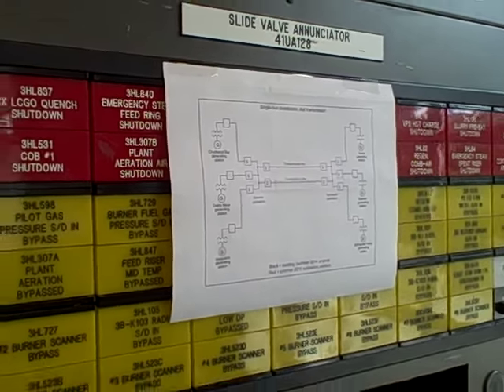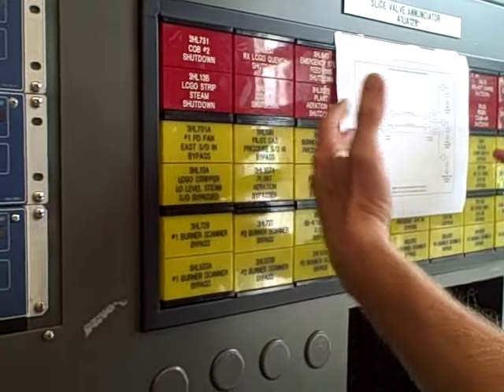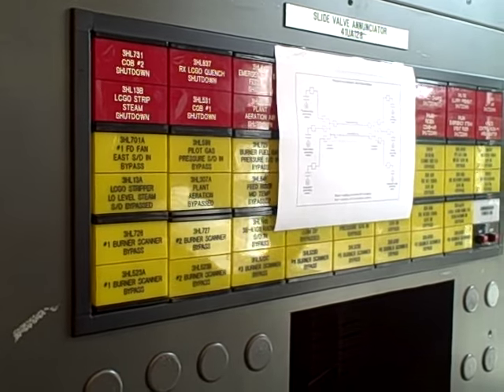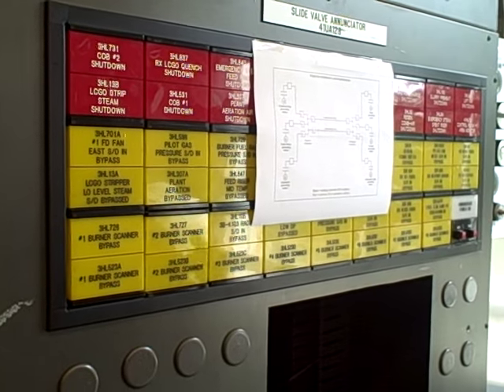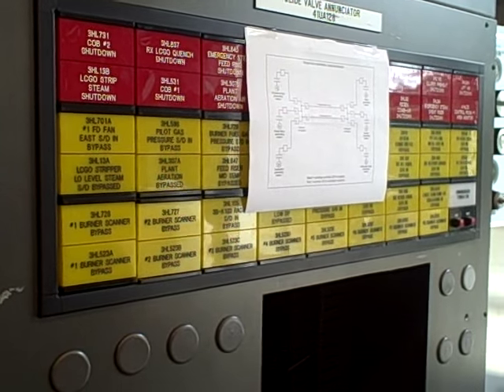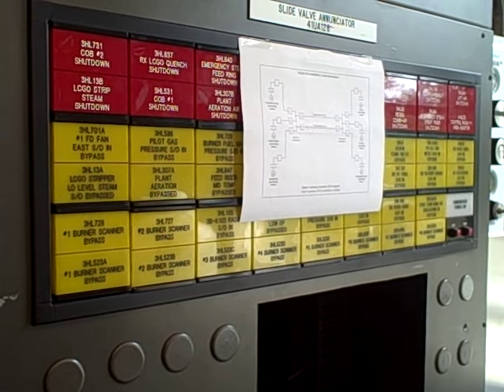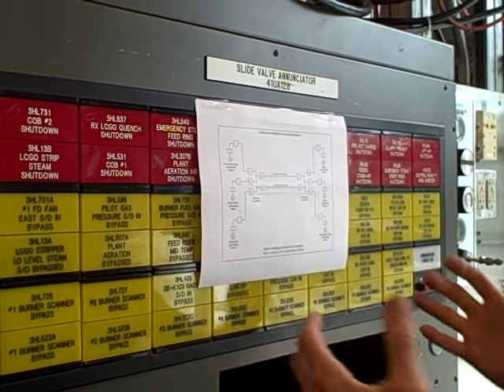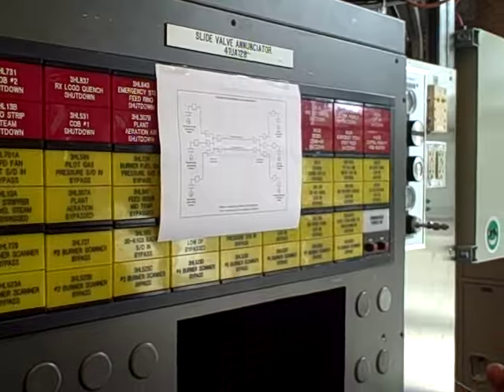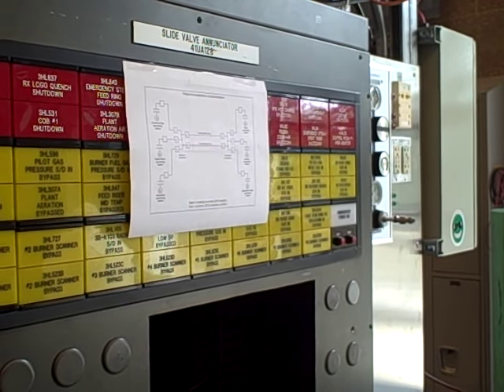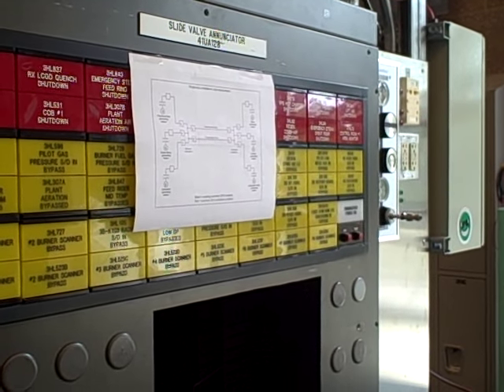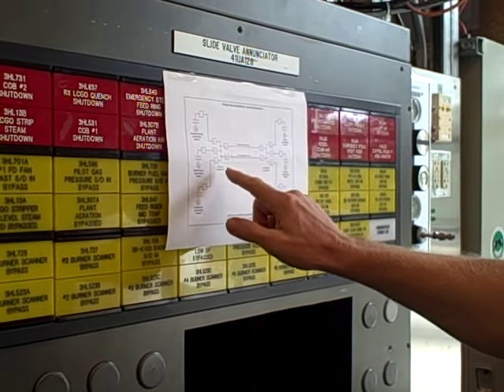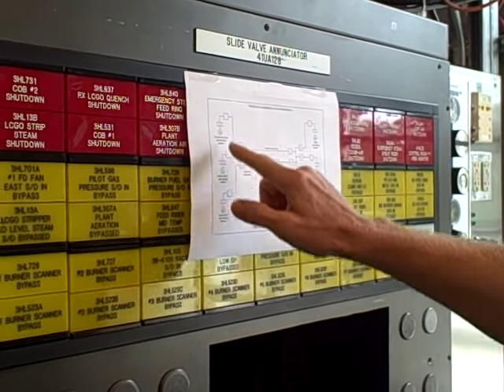So what we're doing with this system is we're able to tie six generators together, synchronize them all with each other. And at present we don't have any permanent loads wired in. So really it's just a big system for synchronizing a bunch of generators. But our purpose in doing this was to demonstrate protective relaying and to be able to wire up protection for our substation zones and for our generators.